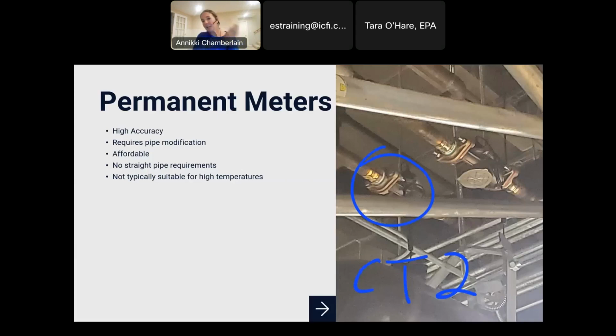Okay, so I can't use existing meters. What kind of permanent, what do I think about if I'm gonna install a permanent meter? Well, it's a good choice if you can do it, right? So they're high accuracy, they're gonna be more accurate than a clamp-on meter, but it does require pipe modification. So it's just the trade-off. They're affordable, they're a lot more affordable than clamp-on meters, and there is typically not a real straight pipe requirement, right? You can kind of put them where you need, but they're not usually typical for high temperatures.